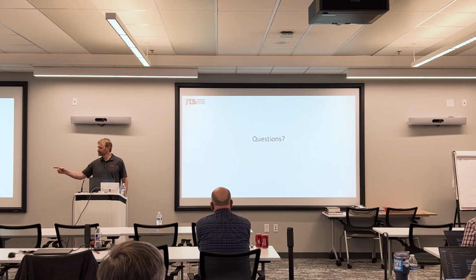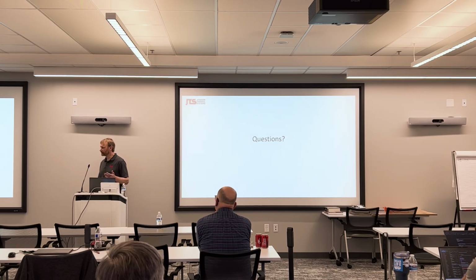Quick question for you. Yes, sir. So you guys have a product line for the A2Ls currently? Yeah, we do. What are you guys doing as far as leak mitigation? Because you have to detect there's a leak. Yeah, so most of our products are outdoor products. A particular product is an air-cooled liquid chiller. It's an outdoor application, and UL really doesn't have any limits on that. Now, if we were to install that chiller indoors, all of a sudden leak detection and exhaust valves and stuff like that come into play.